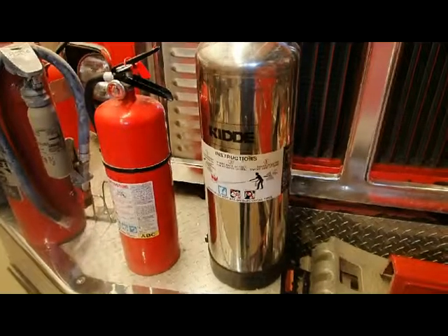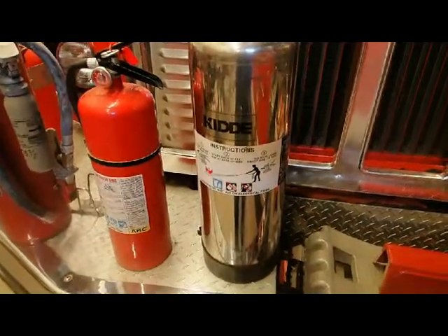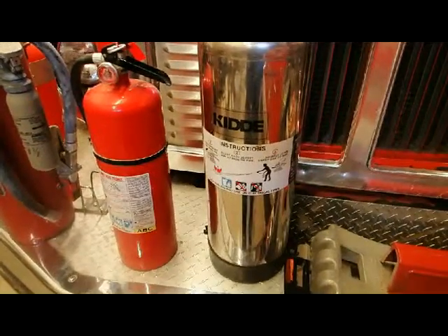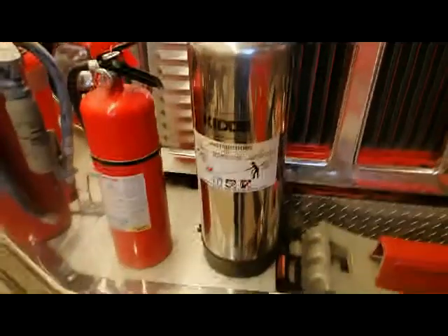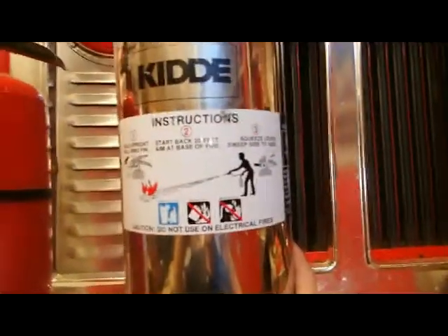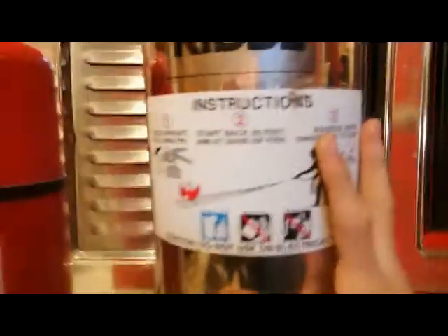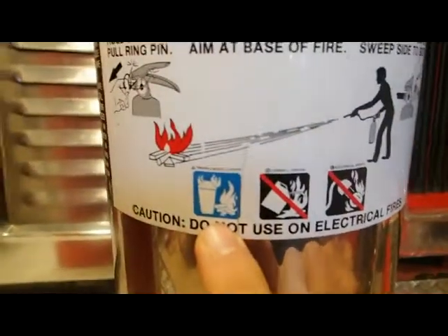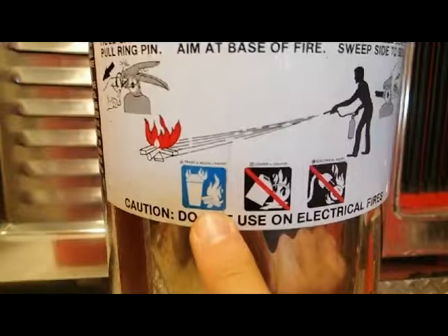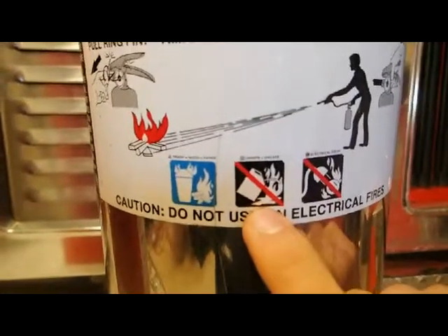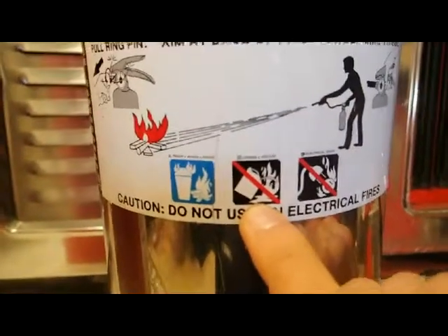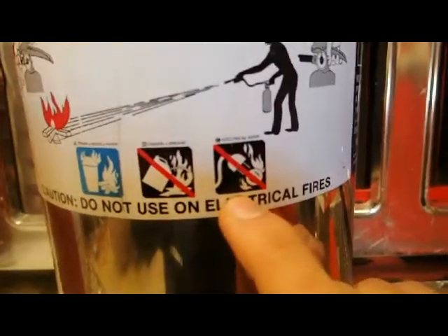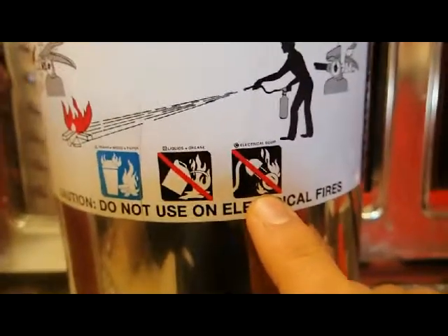So now that we've talked about the different types of fires we're going to be dealing with and the labeling system for our extinguishers, we're going to actually look at some here and see what they look like. The first one we're going to look at is our stored water, and it's basically just going to be applicable only for Class A fires, or your ordinary household combustibles. As you can see here, it has the Class B fires, which are flammable liquids, crossed out, and the Class C fires, which are charged electrical equipment.